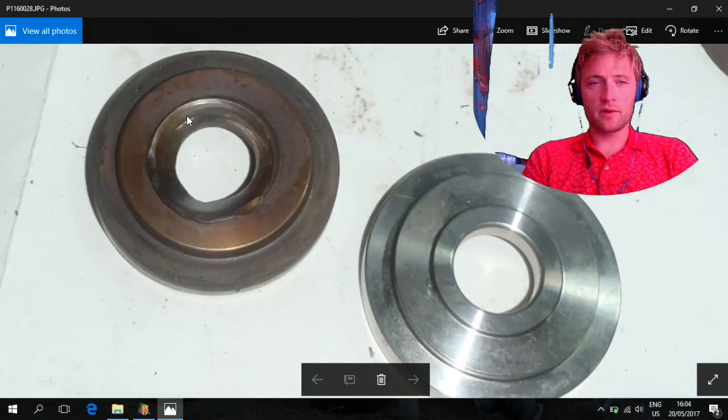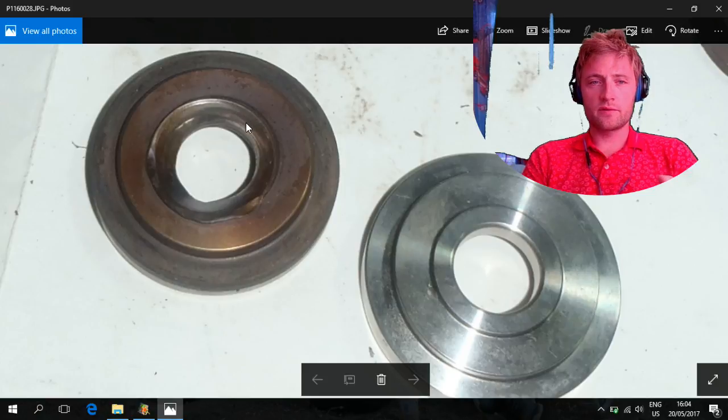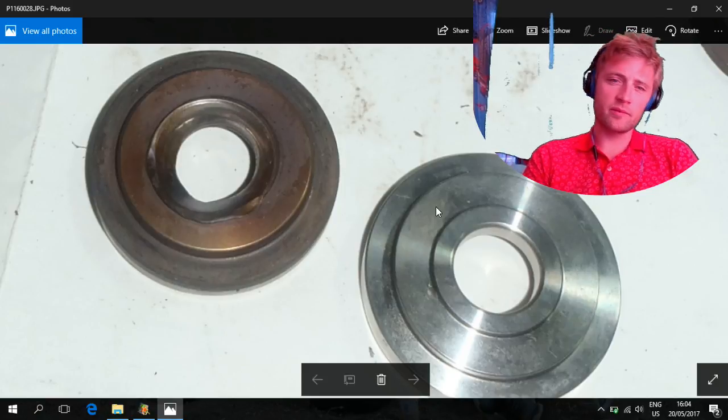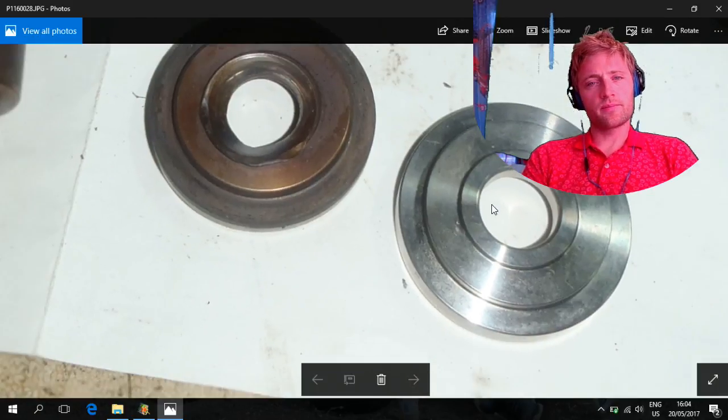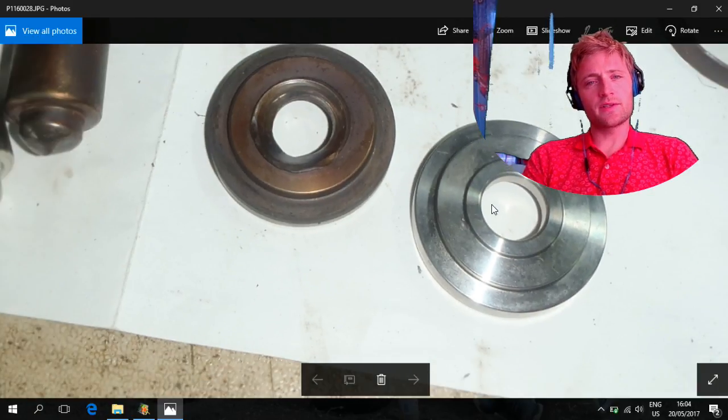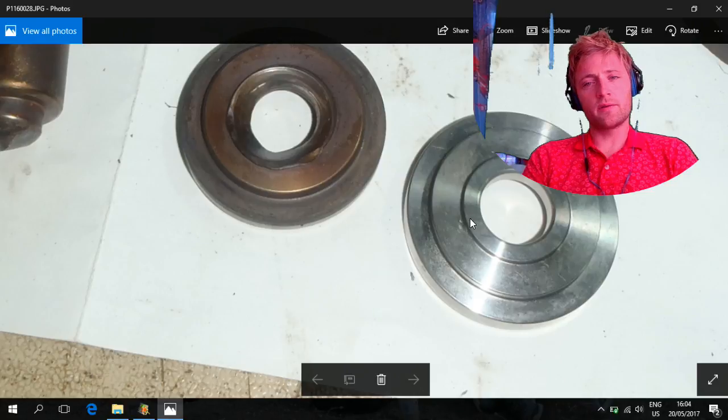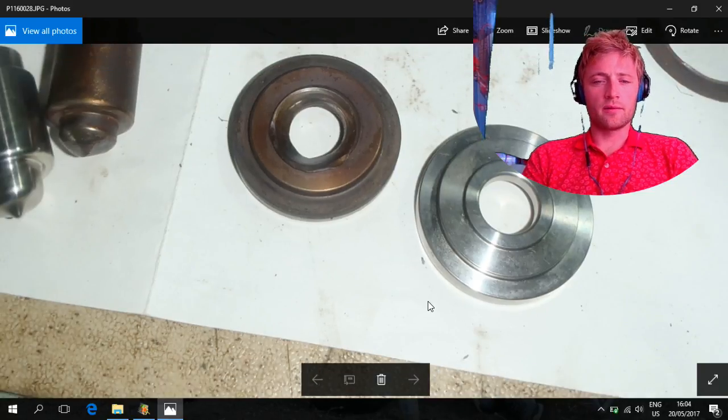This is the same seat. Look here, it's missing the metal. It was so many times pressed and the pressure from the steam destroys everything. Same design but the metal is completely missing.